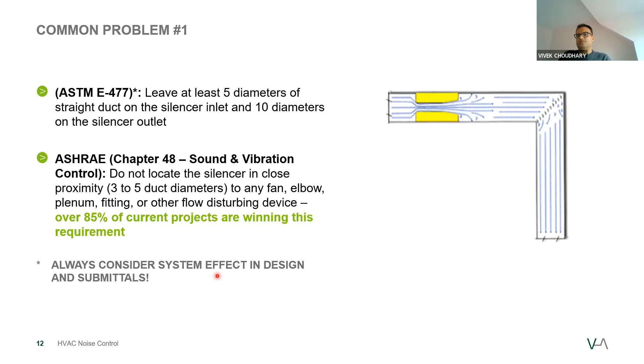So we need to consider these are ideal conditions, and figure out the real system effect conditions after the silencer is installed to calculate the system effect pressure drop. Let's take an example: a straight duct silencer installed right after an elbow, with straight duct after the elbow. If we considered this from a catalog point of view, the ideal pressure drop would be 0.15 inches at 1,000 feet per minute velocity.